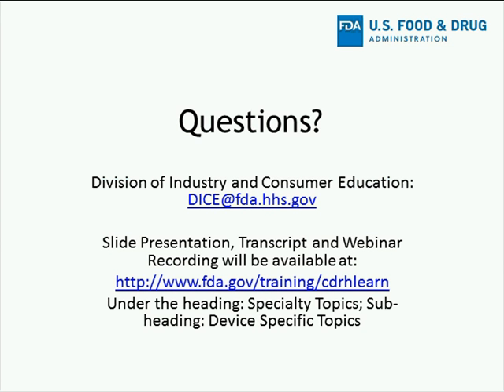Right. Hi, this is Leslie again. There are two aspects to that testing. For the disinfection efficacy, where you're demonstrating that the disinfectant is effective against hepatitis B, you can use parts of the meter. So it's called coupons. So every external part, like the buttons, the display, the case, can be used. But you don't have to use the complete full device. But for the robustness testing, which is the second component to the testing, the entire complete device should be used.